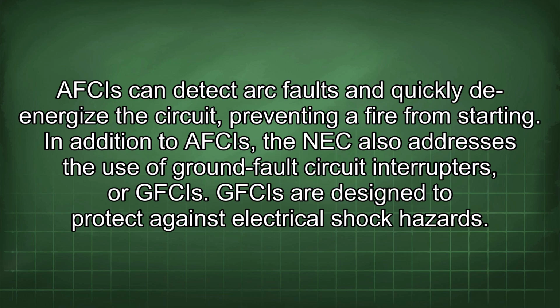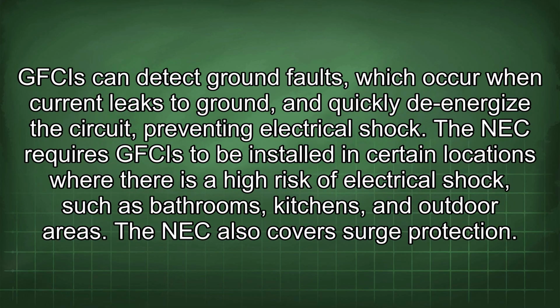In addition to AFCIs, the NEC also addresses the use of ground fault circuit interrupters, or GFCIs. GFCIs are designed to protect against electrical shock hazards. GFCIs can detect ground faults, which occur when current leaks to ground, and quickly de-energize the circuit, preventing electrical shock. The NEC requires GFCIs to be installed in certain locations where there is a high risk of electrical shock, such as bathrooms, kitchens, and outdoor areas.